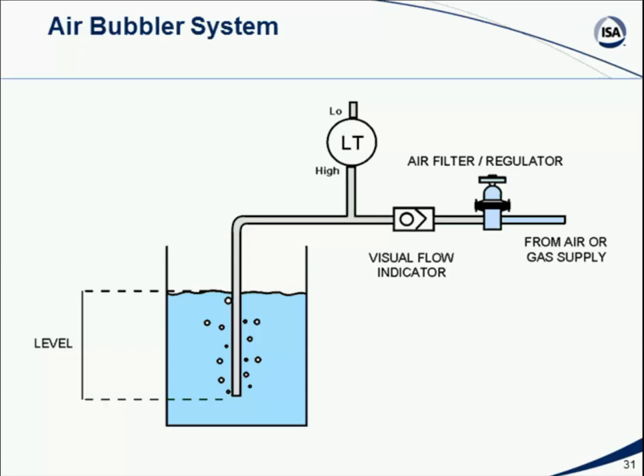And if we make a measurement of that, here we show an indication of that where we've got a level transmitter that again is a differential pressure measurement. It's measuring the pressure of atmosphere on the low side, because again this is an open tank, against the pressure that has to be pushed down through the pipe to keep the bubbler from having fluid in it. That pressure differential gives me exactly the same kind of capability as any other hydrostatic measurement, and I can compute the level in the tank from that. So a bubbler system is another commonly used mechanism, especially in dirty applications where the fluid isn't something as nice as water.